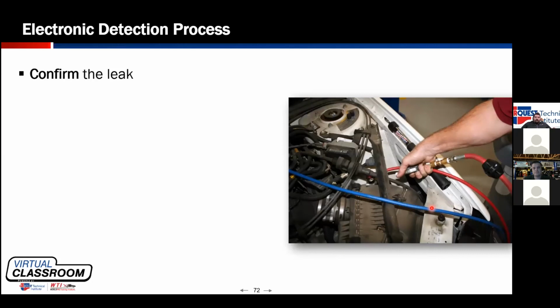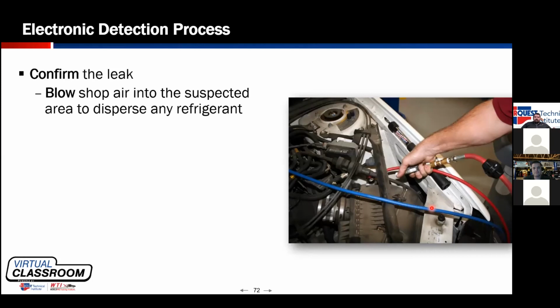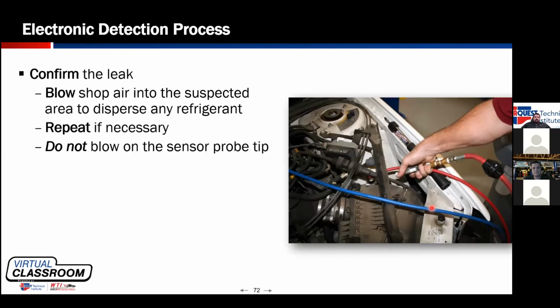If we find something, confirm it. In order for your test to be accurate, it needs to be repeatable. That means that if I find a leak, I should be able to take my leak detector away, let it clear, go back, and it triggers again. If you suspect you've got a buildup of something, hit it with clean, dry shop air, and go back. See if it false triggers again. Never blow compressed air into the tip of your leak detector.